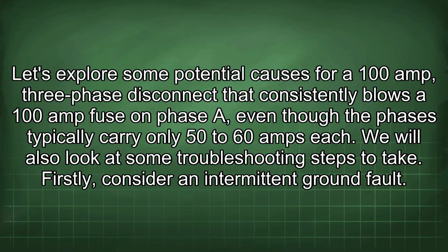Let's explore some potential causes for a 100 amp 3-phase disconnect that consistently blows a 100 amp fuse on phase A, even though the phases typically carry only 50 to 60 amps each. We will also look at some troubleshooting steps to take. Firstly, consider an intermittent ground fault.